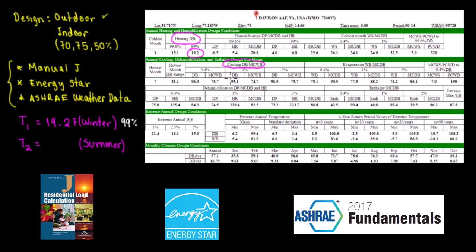So we have our two temperatures — Temperature 1 and Temperature 2. Temperature 2 for summer is 93.1°F at the 1% percentile. If you want to be more conservative you can choose 0.4%, where the temperature is higher at 96°F.